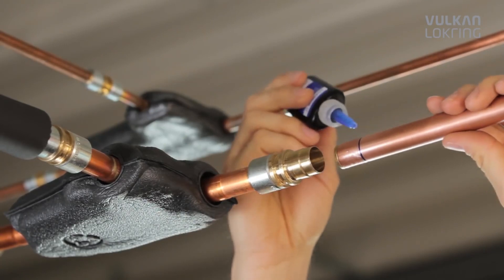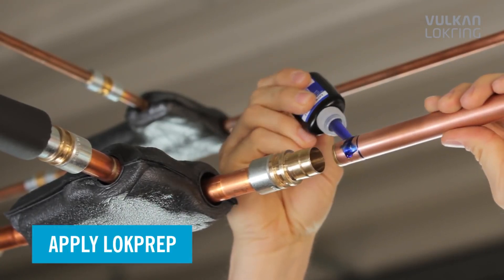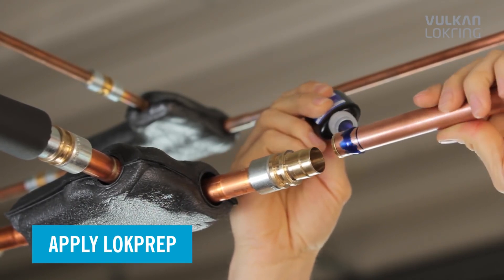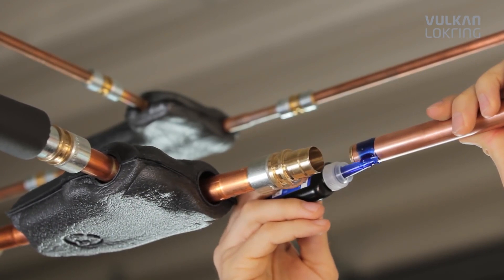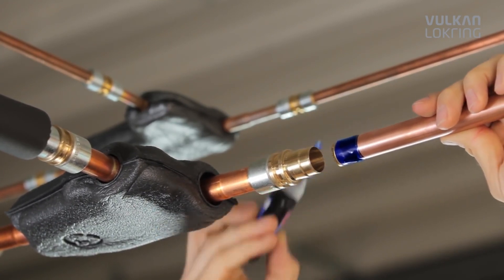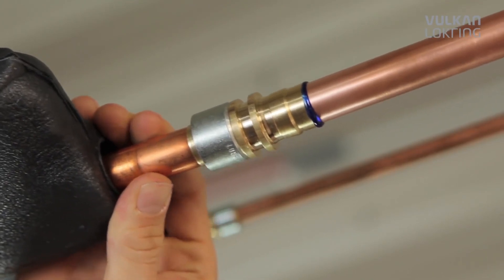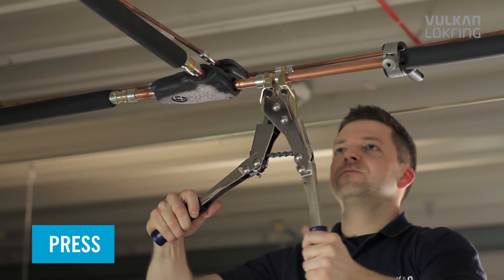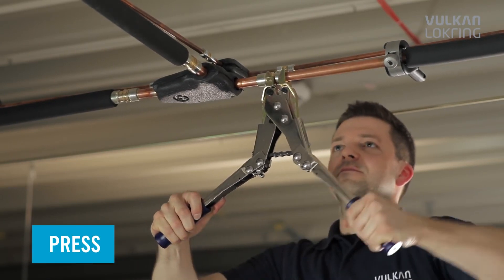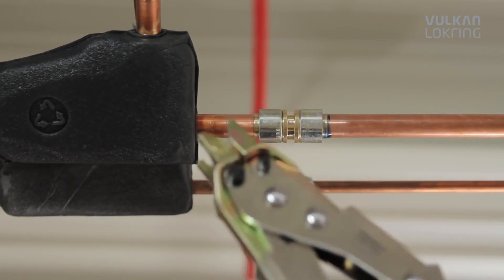Then apply Lokprep evenly to the entire tube circumference. Lock prep penetrates even the finest cavities and fills them completely. Now push the tube end all the way into the connector, and press the Lokring onto the connector using the hand assembly tool. Finished.